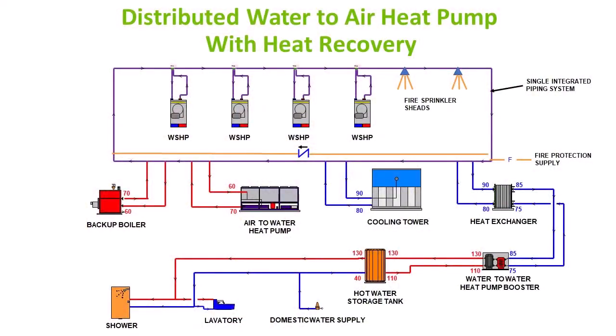Okay, we're talking the fire sprinkler? Yeah, the fire sprinkler system. Okay. Independent heads are technically dead then. Yes, but that's not domestic water. Okay. We're not using the water in the fire sprinkler system for domestic water. We don't care anything about Legionella in that enclosed system. It's just a normal hydronic system, right? If you're doing this system, then you need to worry about it, right? That's domestic water, and I need to worry about Legionella.